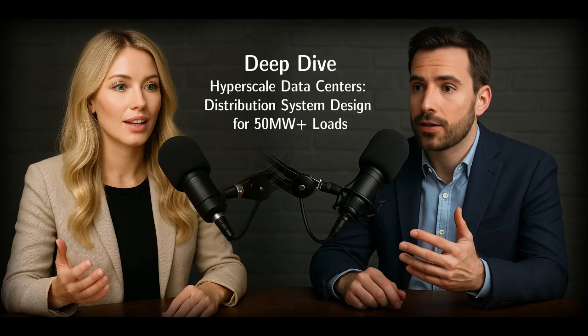Like what? Well, first, you cut the current roughly in half compared to 12.47 kilovolt for the same power. That immediately helps with voltage drop over distance. You get much better voltage regulation. Makes sense. Lower current, lower drop. Exactly. It also usually enhances reliability because you often have more options for backup feeds or loop configurations at these voltages, and it gives you more flexibility for future load growth.